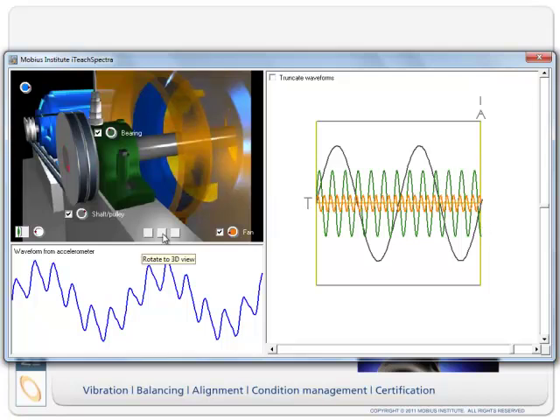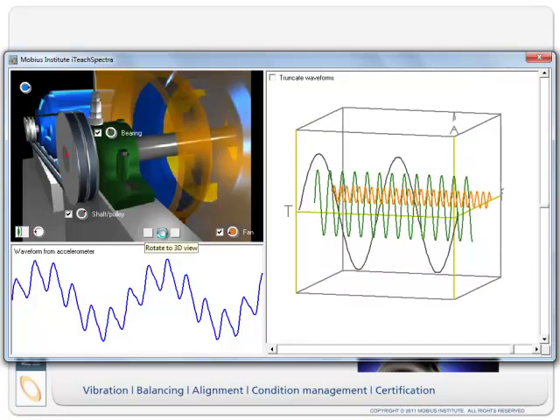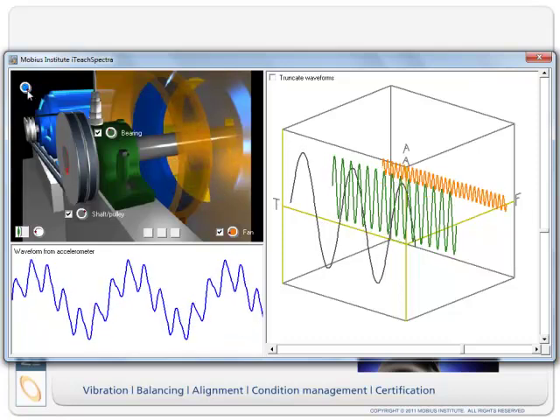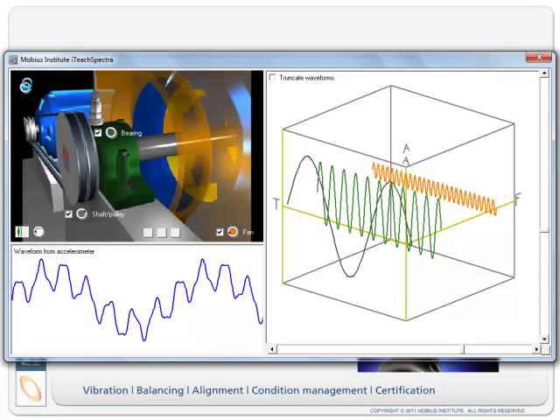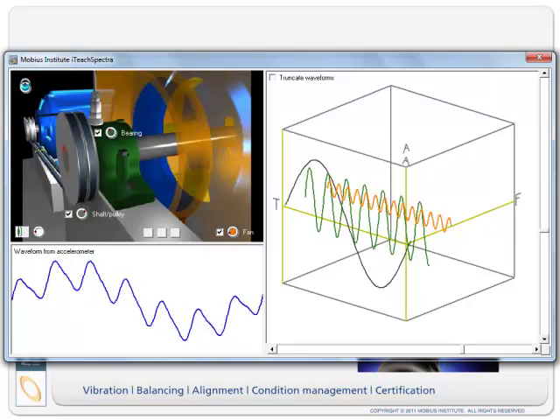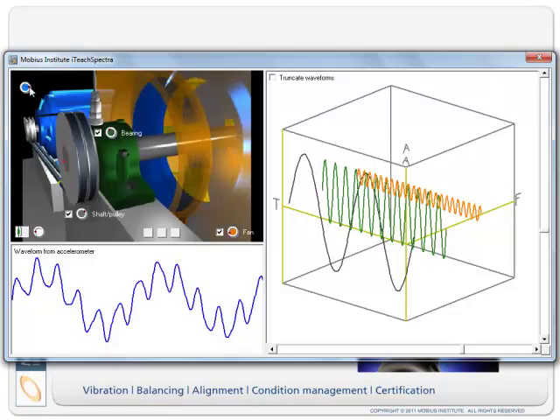But by asking the cube to rotate just halfway around, now we see the introduction of frequency. We have frequency along this side of the cube. So if I speed the machine up, which increases all the frequencies, you can see the waveforms move further along up into the higher frequency area. If I slow the machine down, then they're all up closer to this end. Yes, the shape of the waveform changes, but I've positioned the waveforms along this axis here, which is related to frequency. So I'll just put them back in a nice spot. So that's all good.